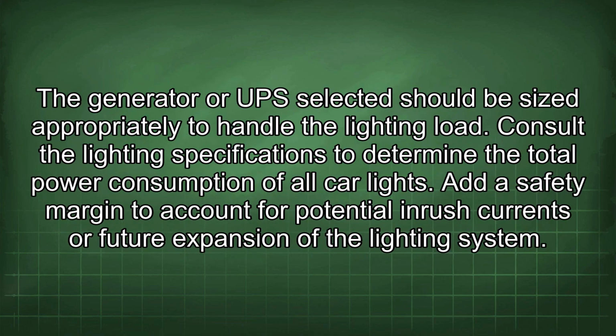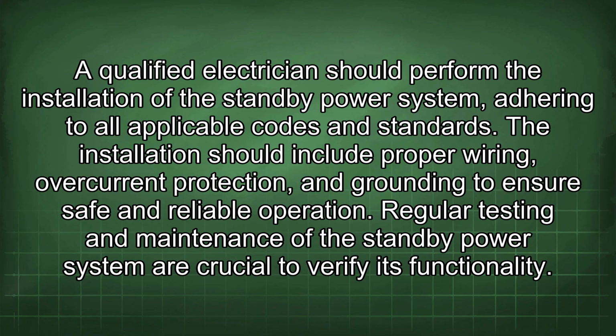The generator or UPS selected should be sized appropriately to handle the lighting load. Consult the lighting specifications to determine the total power consumption of all car lights. Add a safety margin to account for potential inrush currents or future expansion of the lighting system. A qualified electrician should perform the installation of the standby power system, adhering to all applicable codes and standards. The installation should include proper wiring, overcurrent protection, and grounding to ensure safe and reliable operation.